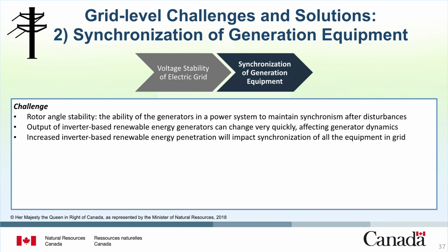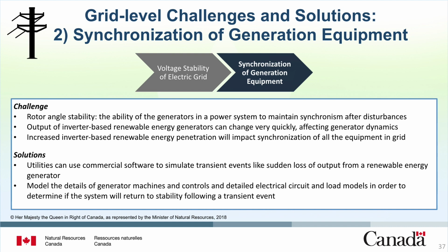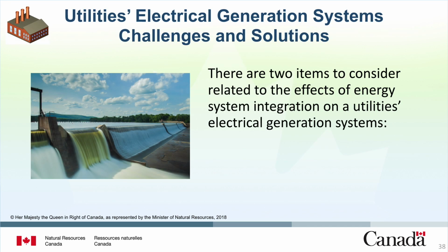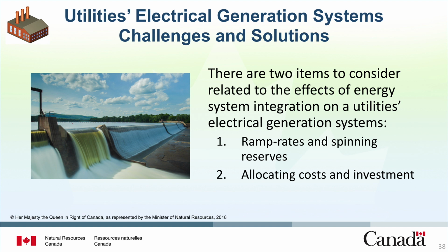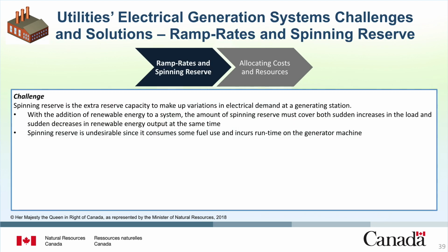In terms of solutions, utilities can use commercial software packages to simulate transient events, such as a sudden loss of output from a renewable energy generator. Software tools can model the details of generator machines and controls and detailed electrical circuit and load models in order to determine if the system will return to stability following a transient event such as sudden change in the output of a specific renewable energy generator. The final section on challenges and solutions will discuss two items related to the effects of energy system integration on a utility's electrical generation systems: 1. Ramp rates and spinning reserves, and 2. Allocating costs and investment. Let's begin by discussing ramp rates and spinning reserves.